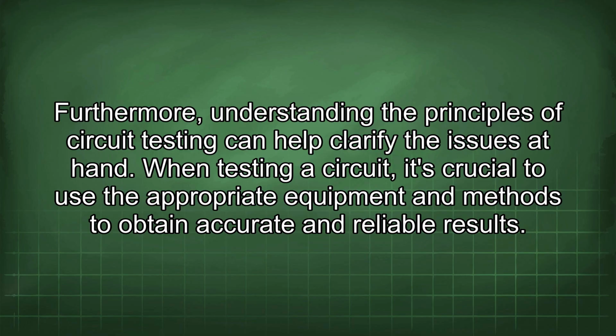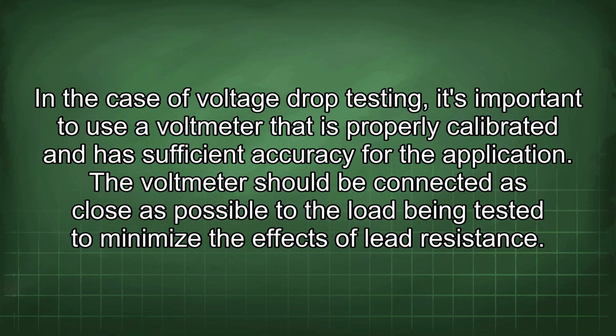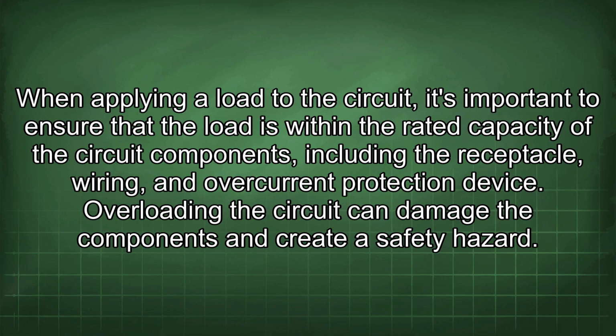Furthermore, understanding the principles of circuit testing can help clarify the issues at hand. When testing a circuit, it's crucial to use the appropriate equipment and methods to obtain accurate and reliable results. In the case of voltage drop testing, it's important to use a voltmeter that is properly calibrated and has sufficient accuracy for the application. The voltmeter should be connected as close as possible to the load being tested to minimize the effects of lead resistance. When applying a load to the circuit, it's important to ensure that the load is within the rated capacity of the circuit components, including the receptacle, wiring, and overcurrent protection device. Overloading the circuit can damage the components and create a safety hazard.